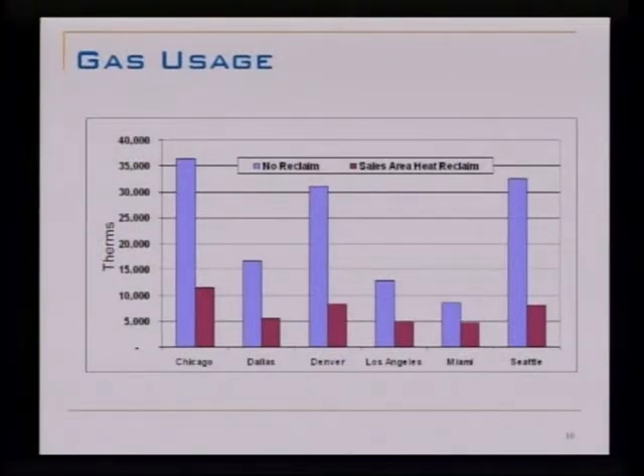This is some data that Doug Scott, again from Vacom Technologies, modeled with DOE2 for grocery stores in these different climates, and the effect of doing heat reclaim on the gas usage. And you can see in every climate it's a pretty significant measure. The only place where you could argue that it's not as significant is Miami because it's bloody hot down there. But grocery stores most anywhere in the country are unlike any other commercial building in that they're always in heating. And the reason they're always in heating is because there are all these refrigerated cases sitting out on the floor holding ice cream and frozen chickens and so forth. So it gets really cold and you've got to heat them up. So heat reclaim can be a very big portion.